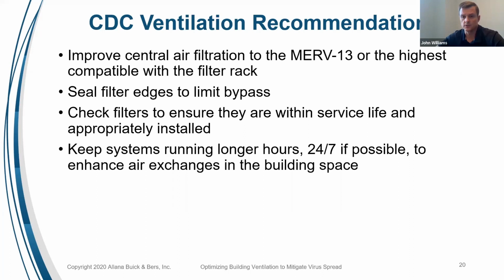I've seen filters in properties close to airports that needed changing monthly, even on return air units. The other thing we'll talk about too is increasing your filter efficiencies. And as we go to higher efficiency filters, they're going to load up faster. They're going to collect more in the filter, and they're going to require more frequent filter changes. So as you increase your filter efficiencies, you might find that your change out frequency increases also. You're talking about the MERV 13, John, with the higher efficiency filters? That is correct, Kareem. And we'll be touching on that in a moment also.